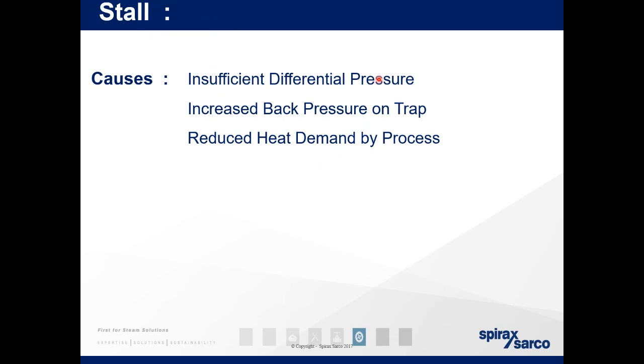I'm not sure how many of you have seen a leaking heat exchanger in your process. Often, not always, that is caused by stall. It's where you get a backup of water in your heat exchanger and you reach a point, say it's 50% full of water, just for the sake of argument, and 50% full of steam. Where the steam meets the water, there is going to be a difference in heating temperature.